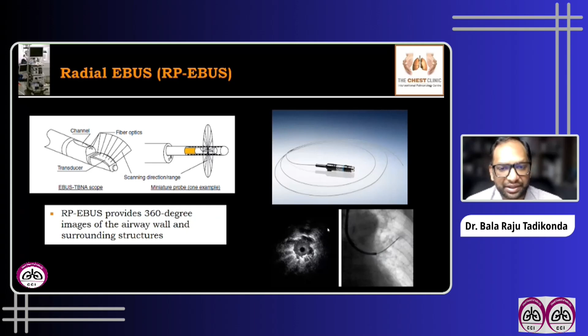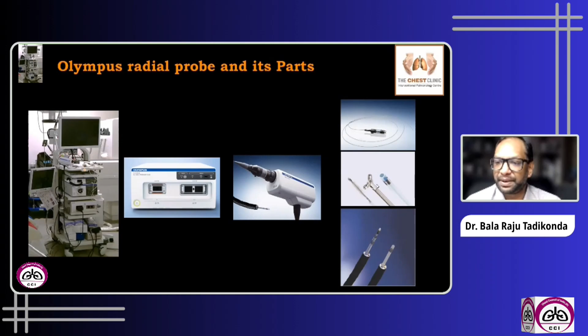Coming to the different parts of radial EBUS. The first thing you require is an ultrasound processor. This is an Olympus ultrasound processor which has the connections for radial EBUS and the convex EBUS. The next thing, to rotate 360 degrees, you require this probe driving unit, and that's the radial EBUS. This radial EBUS has to be passed through the working channel of the bronchoscope. And if you have a guide sheath, this can be passed through the guide sheath in the working channel of the bronchoscope.